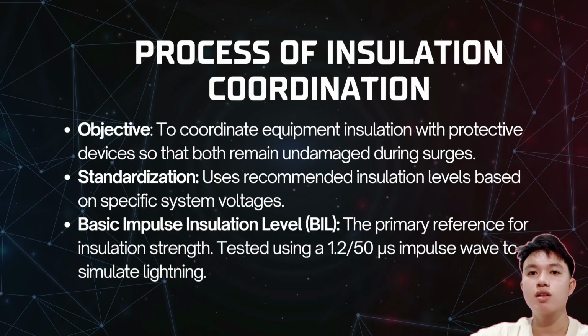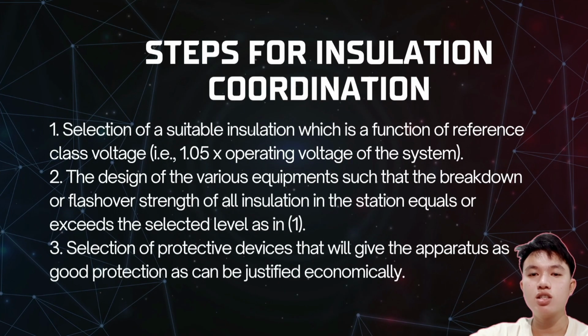Basic impulse insulation level. The primary reference for insulation strength tested using a 1.2/50 microsecond impulse wave to simulate lightning. The ultimate stress test for insulation, it measures how much voltage an object can handle from a lightning-like surge, specifically using a standard 1.2/50 microsecond wave. Steps for insulation coordination. So first step, selection of suitable insulation, which is a function of reference class voltage 1.05 times operating voltage of the system.